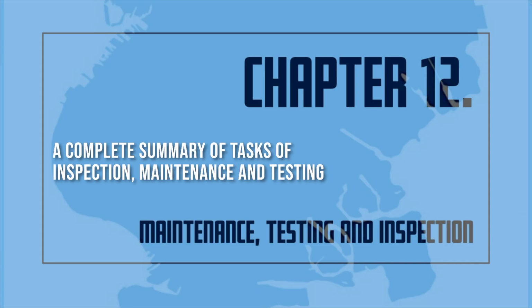Alarm devices. Alarm devices shall be inspected quarterly to verify that they are free of physical damage. Hydraulic nameplate. Hydraulically designed systems shall be inspected quarterly to ensure that the nameplate is attached securely to the sprinkler riser or sprinkler control valve and is legible. Buildings. Annually, prior to freezing weather, buildings with wet pipe systems shall be inspected to verify that windows, skylights, door ventilators, other openings and closures, blind spaces, unused attics, stair towers, roof houses, and low spaces under buildings do not expose water-filled sprinkler piping to freezing, and to verify adequate heat with a minimum temperature of 40 degrees Fahrenheit.